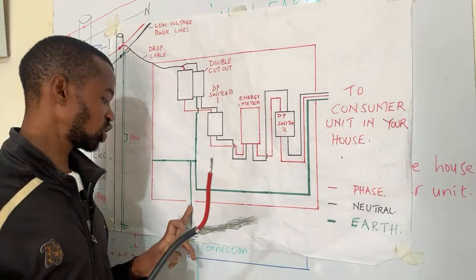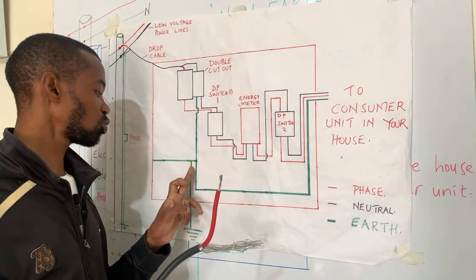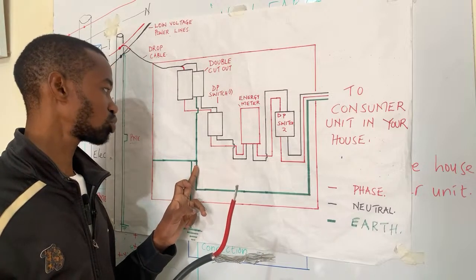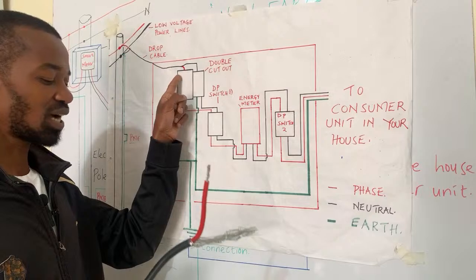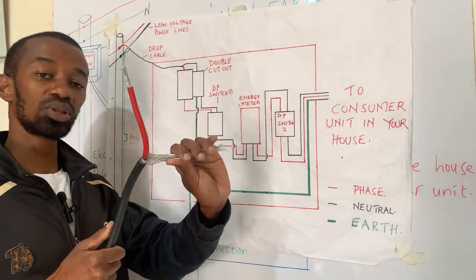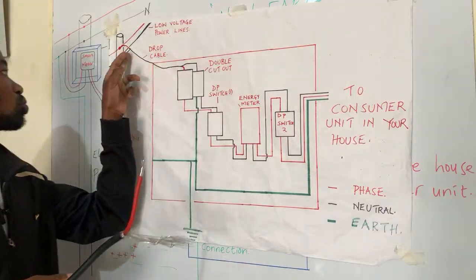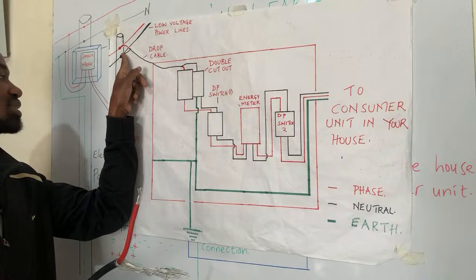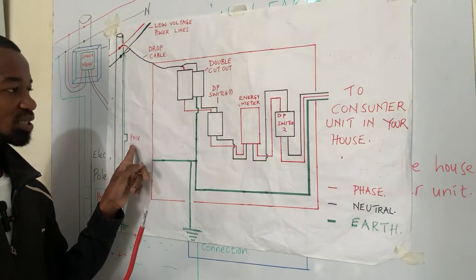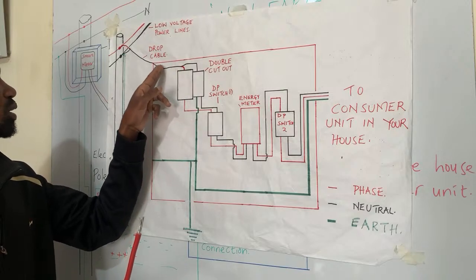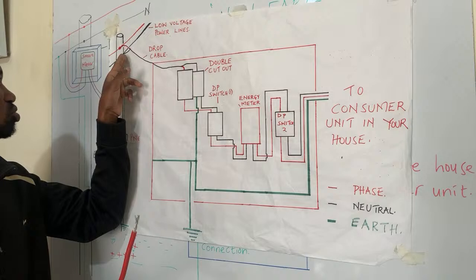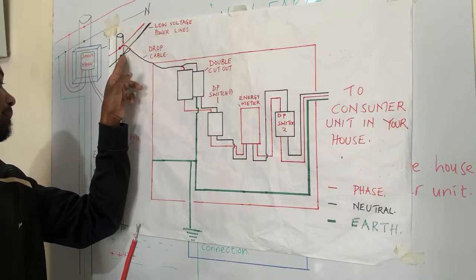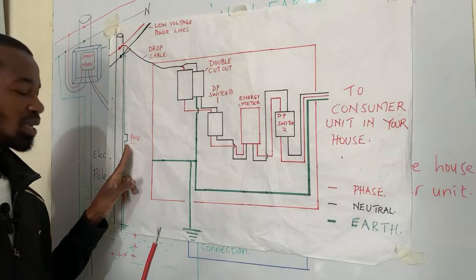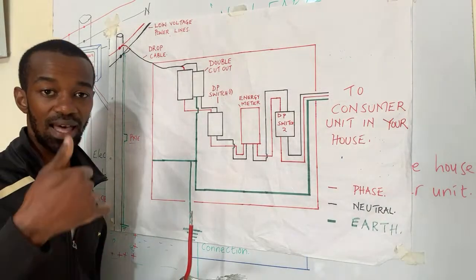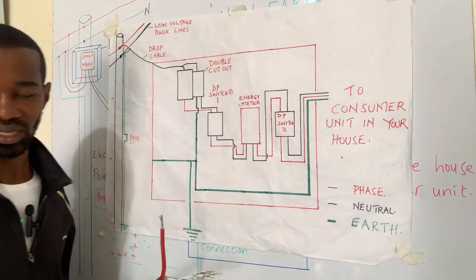So that if there is an issue, and the earthing connection at this particular point is weak or has disconnected due to one or two reasons, then excessive charges will go all the way through this cable, through this neutral connection, to the neutral conductor where it is earthed through the PME. The excessive charges will travel through the drop cable, get to the neutral conductor at the pole, the immediate pole that is serving your customer with power, drop through the PME, protective multiple earthing, to the ground, and then back to the source, which is the transformer.